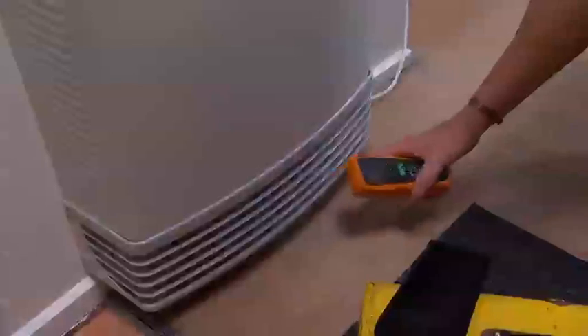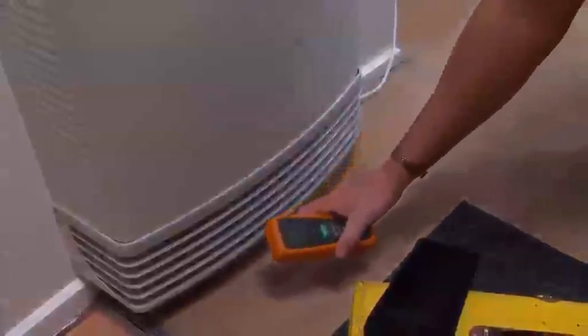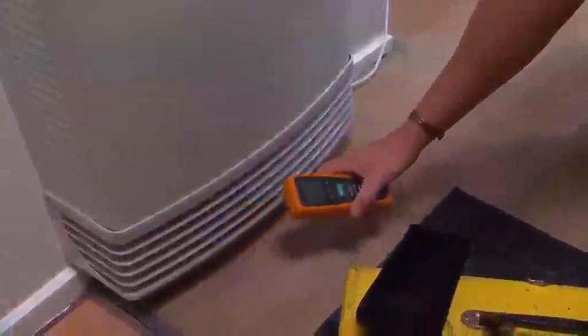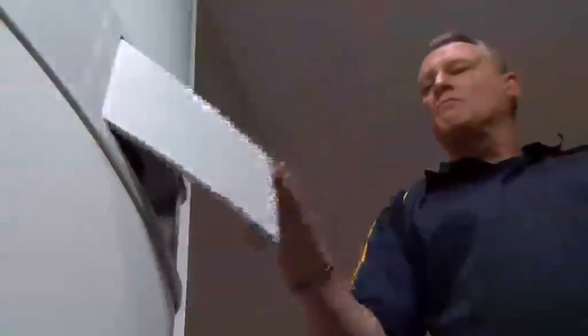The reading on the test instrument should diminish to the original background level reading at the end of the 5-minute test cycle. If not, then the appliance is leaking or spilling CO, and the fault will need to be rectified or the heater disconnected for the safety of the occupants.